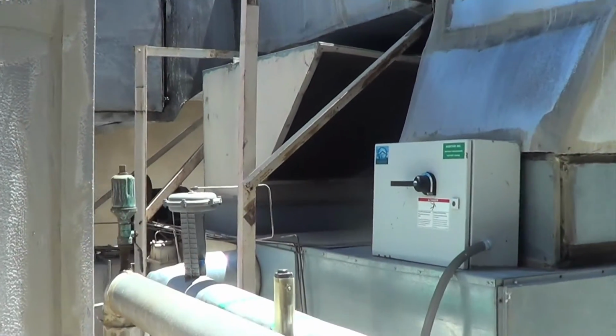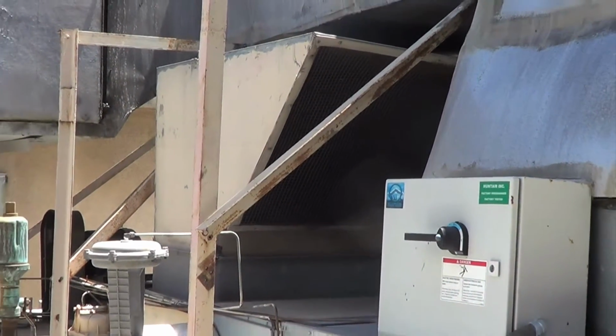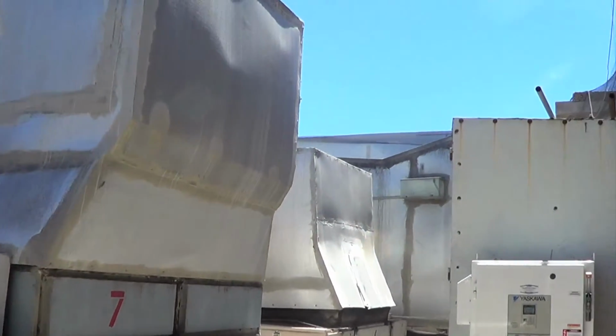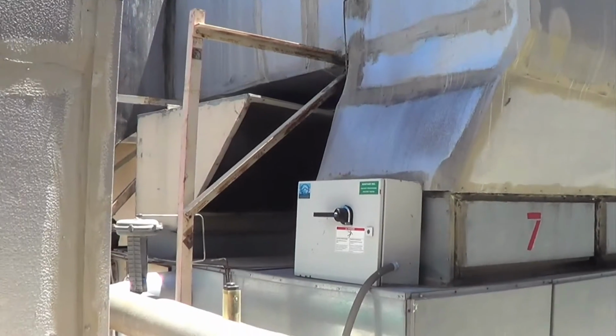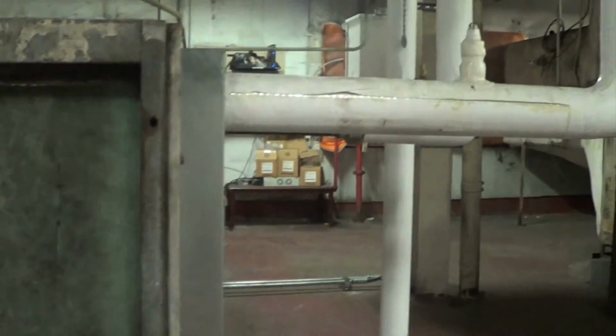There's another air handler with the air intake right there. You see water pipes, so you know the coils are right there. And this is typically what they look like. They all might vary in appearance, but this is pretty common. Now getting back to your pre-filters, here you have the pre-filters. I'll pull them back. Now there's the most important feature right there, coils. Now this is what we're going to focus on right here. This is all you really need to know about to bridge that gap.